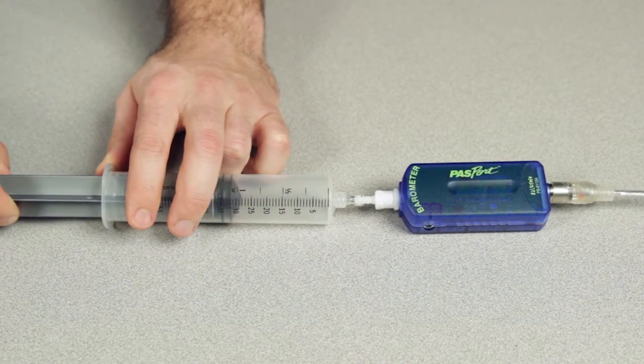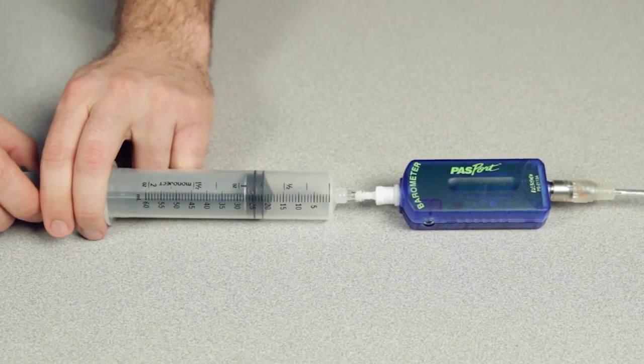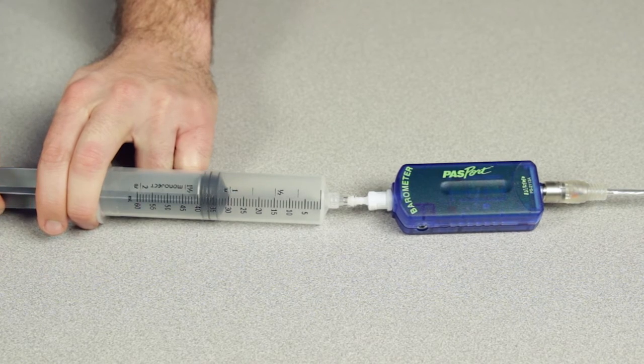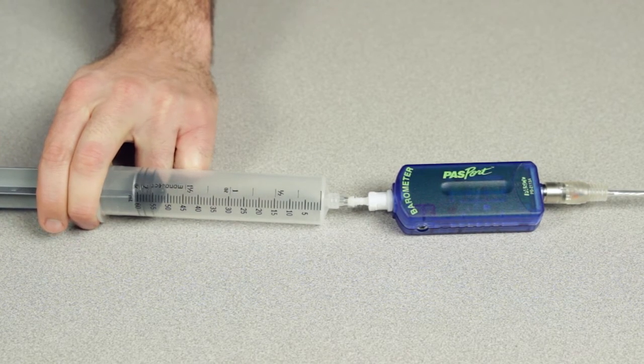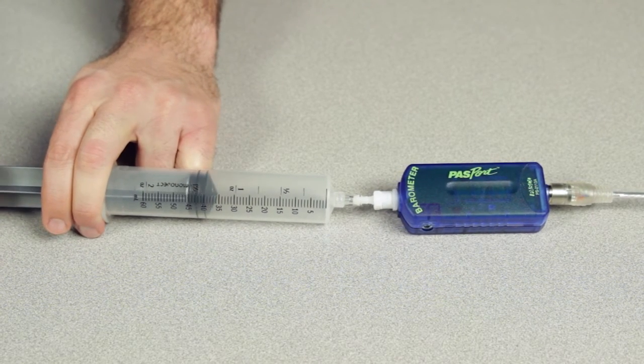When using the barometer low pressure sensor, do not subject the sensor to pressure in excess of 115 kilopascals, nor allow water to enter the sensor's pressure port. Both of these will permanently damage the sensor.